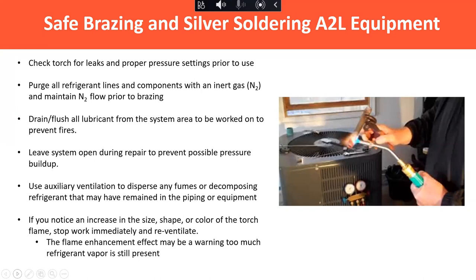And the last bullet down here at the bottom, this thing we call flame enhancement. In the old days, a torch was used as a leak detector in a number of cases. You could walk around with a torch, and if there was any refrigerant around, you would see this change in the flame, a change in color or enlargement. We call it flame enhancement.